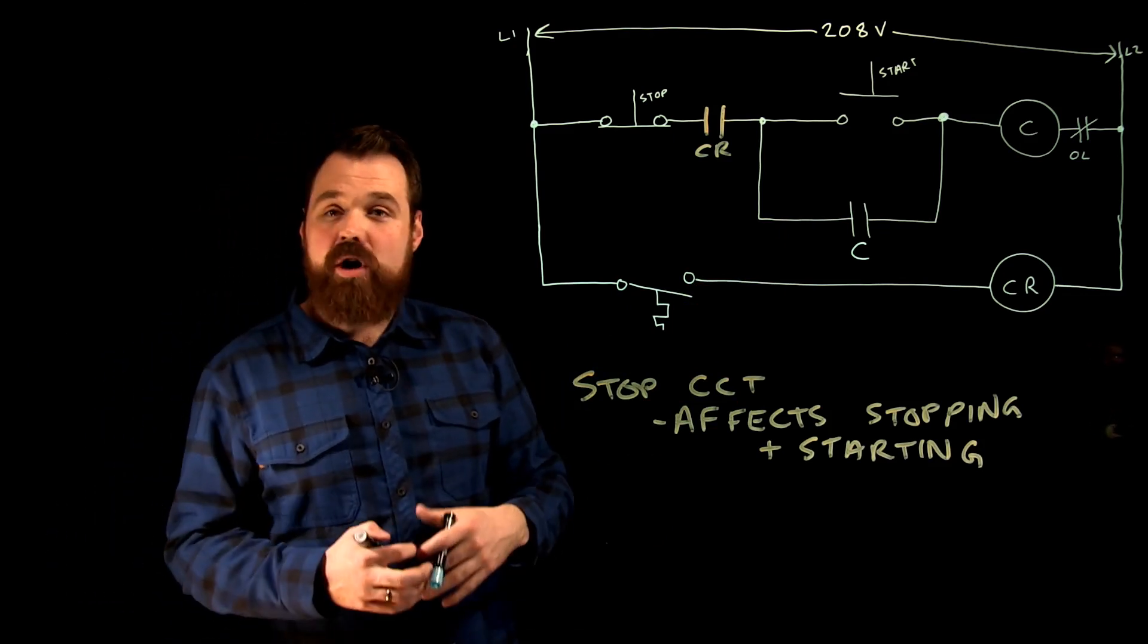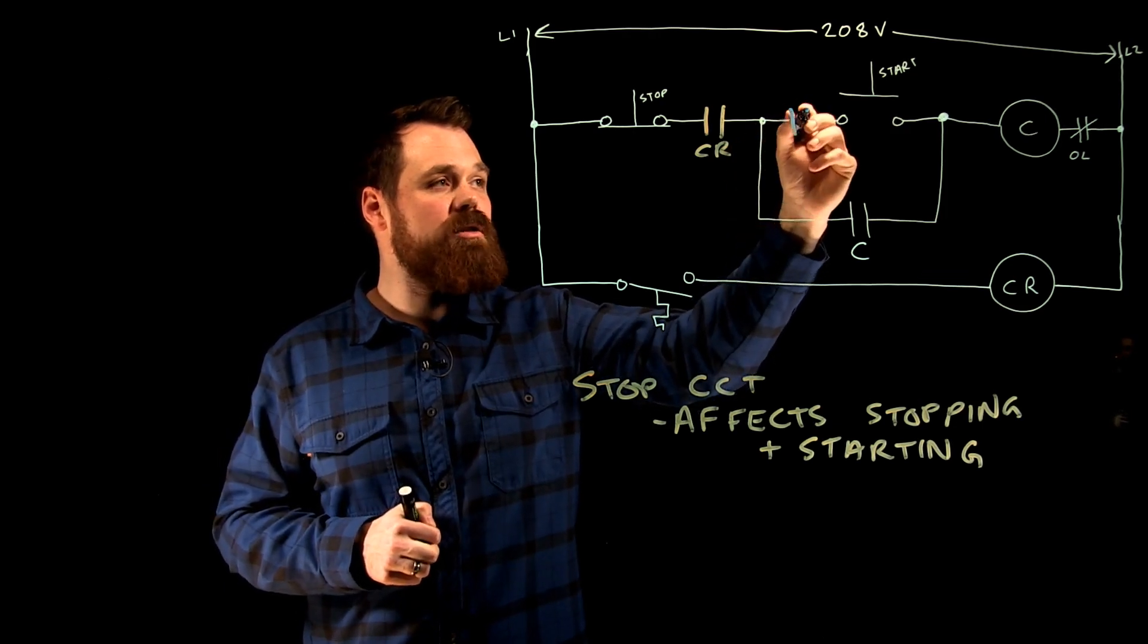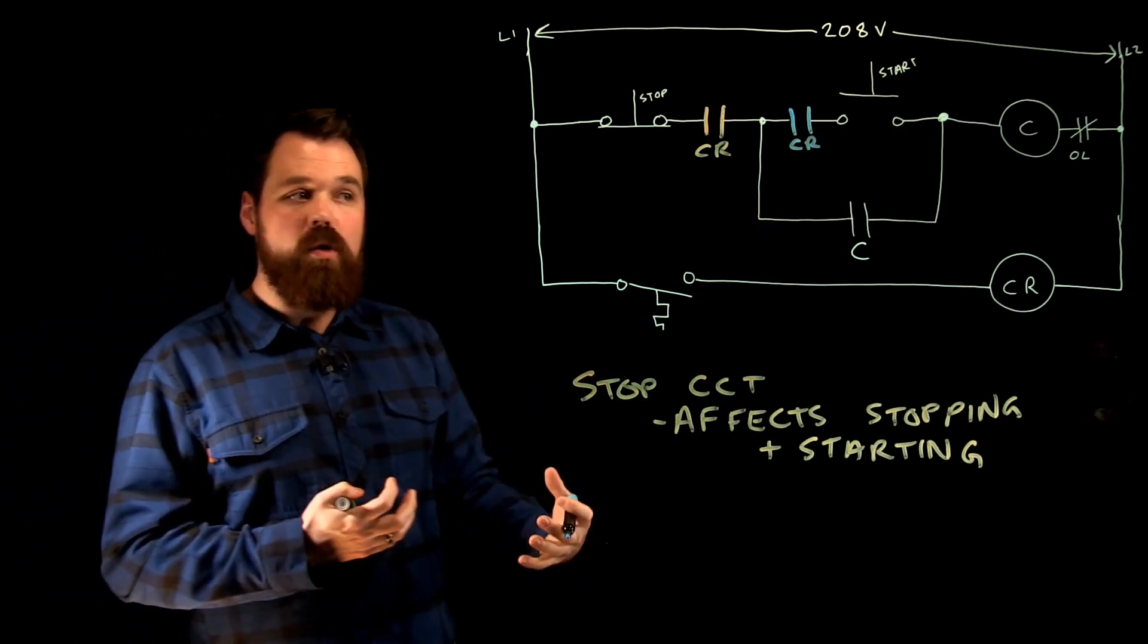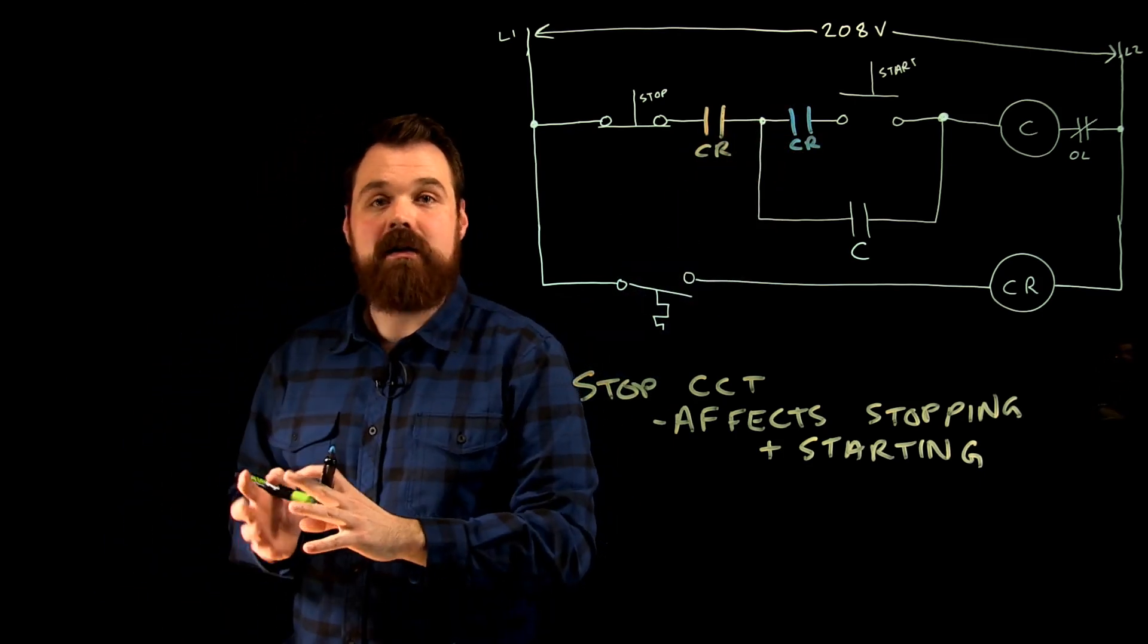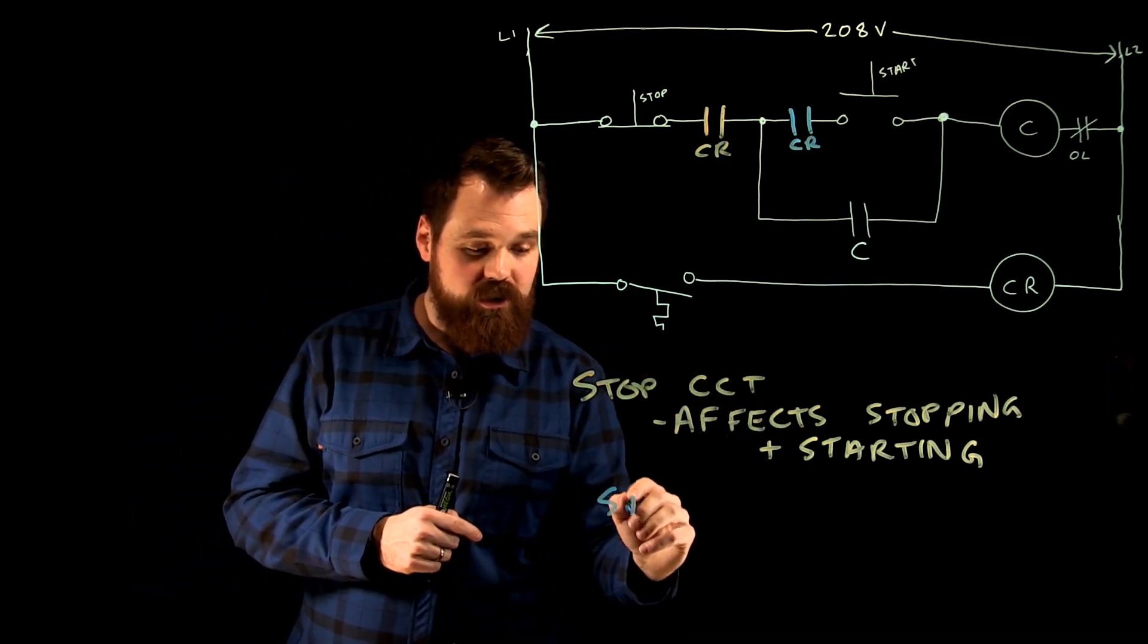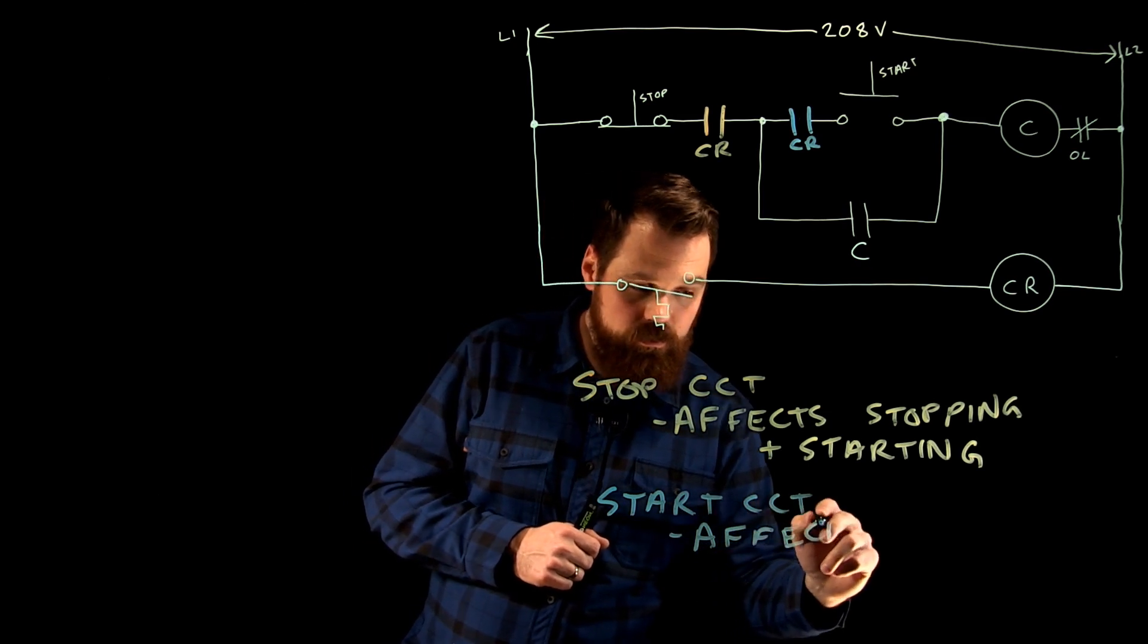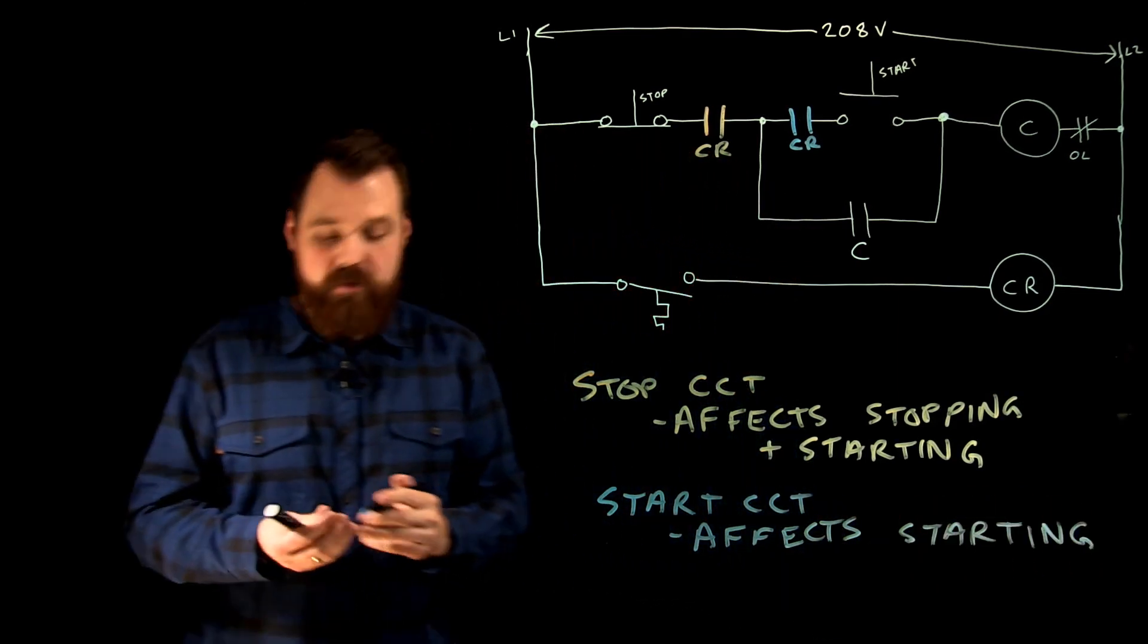Next thing we could do is we could take a set of contacts and we can install it in the start circuit. So if we were to put that right here, just in series with the start button, the only thing that this would affect would be the starting of the motor. So when this set of contacts is open, it just prevents us from starting the motor. But if it's already running, it's going to continue to run. We don't stop the motor. So whenever we put a set of contacts in the start circuit, it really just affects the starting of the motor.